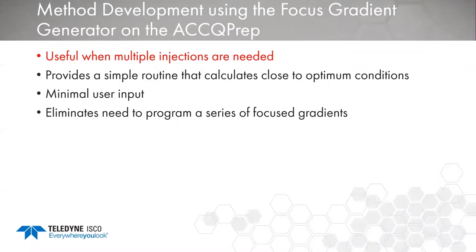When should we invest time in method development? It's most useful when doing multiple injections, since time savings are multiplied by the number of runs. The ACCQPrep software now provides a simple routine that calculates close-to-optimum conditions based on one scouting run — from either an analytical system or a run on the ACCQPrep itself. It requires minimal user input, no calibration if done on the ACCQPrep, and it pinpoints specifically on your peak of interest rather than just giving you a zone, eliminating the need to program a series of focus gradients manually.